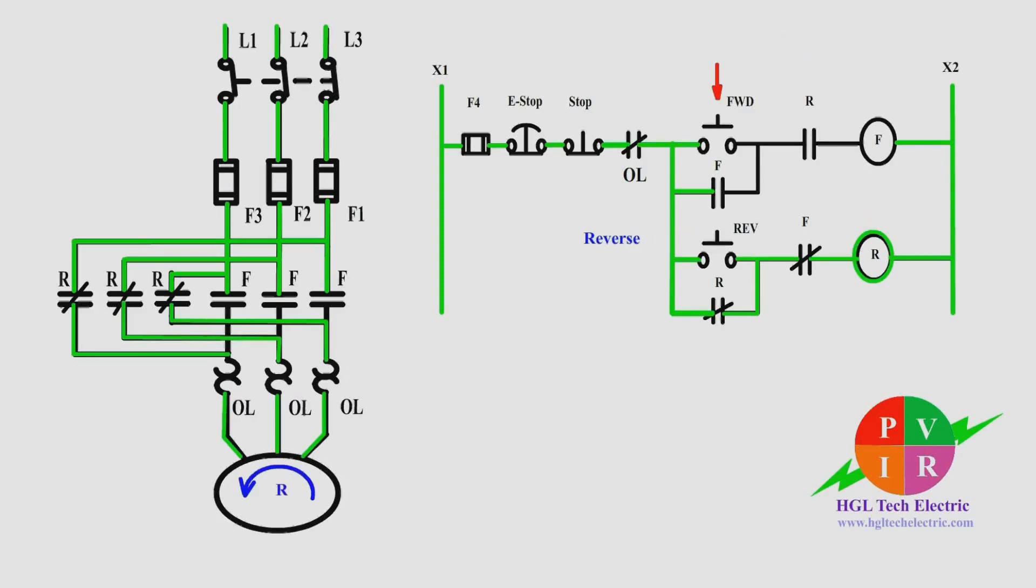Now, in this case, the normally closed auxiliary contact R that is connected in series with coil F is open. Preventing a short circuit from occurring if an operator accidentally presses the forward button.